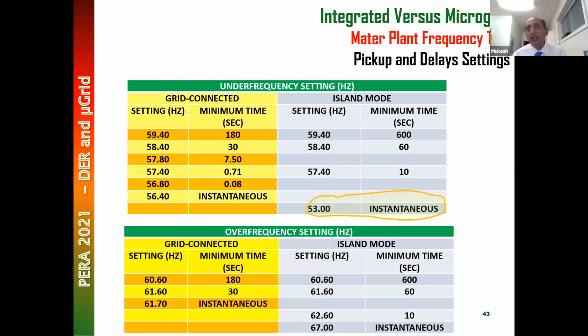The reason, and also I want to tell you, in an islanded mode, 53 Hz is an instantaneous trip. If the frequency drops for any reason to 53 Hz, the microgrid collapses. We trip, we kill the microgrid. At that point, we think the frequency has gone too low. There's no way the microgrid will survive. We kill it.